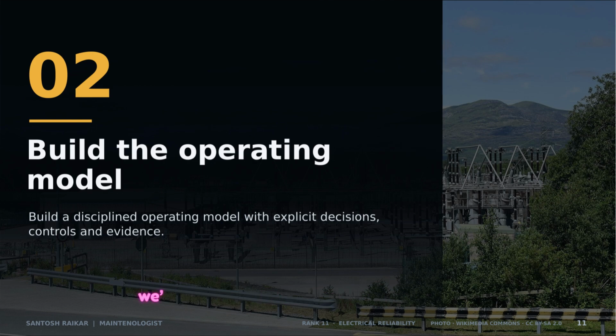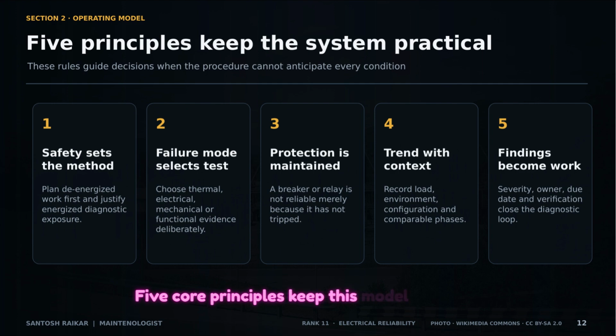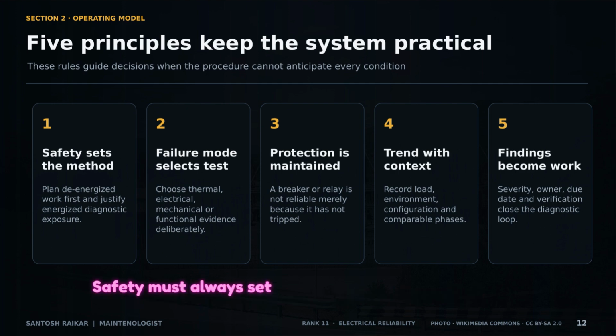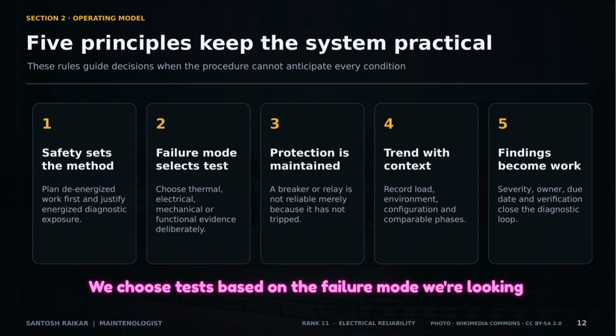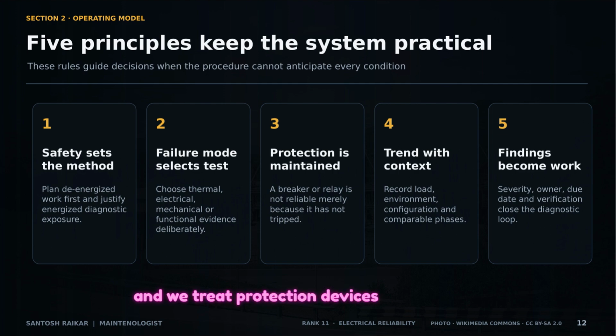In Section 2, we'll look at building the operating model, a disciplined framework with explicit decisions, controls, and evidence. 5 core principles keep this model practical. Safety must always set the method. De-energized work is the default. We choose tests based on the failure mode we're looking for, and we treat protection devices like relays as active reliability systems that need regular maintenance, even if they've never tripped.